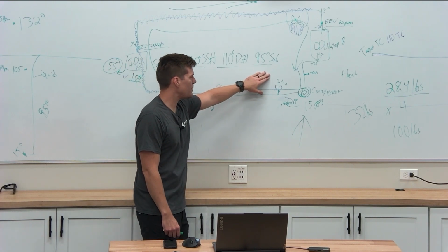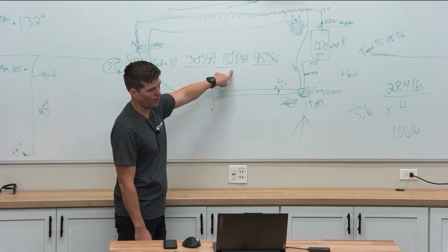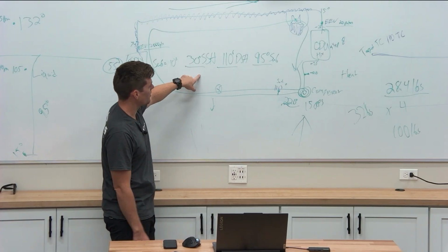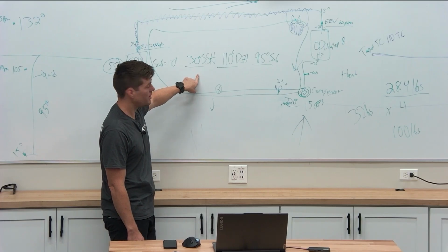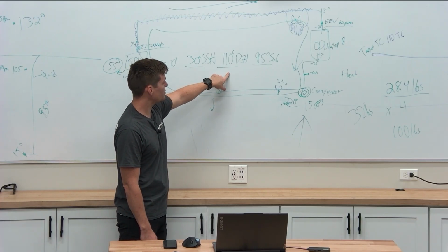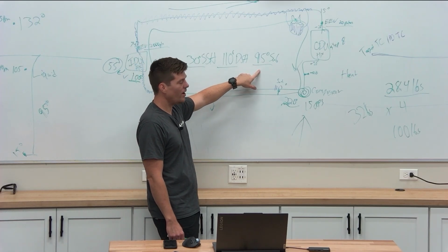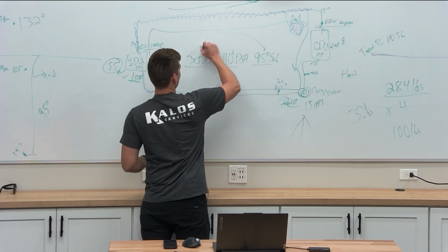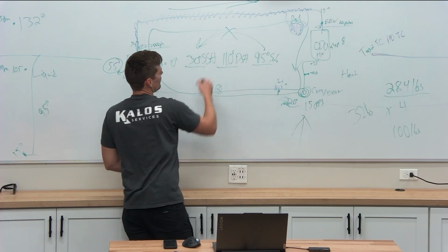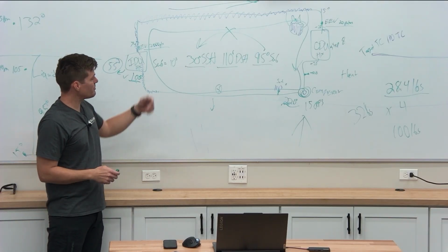All of these numbers paint a specific picture. This means not enough vapor, not enough oil. This means not enough vapor. Right? We know that. High superheat, not enough vapor. High discharge superheat, not enough vapor, not enough oil. High subcooling, wait a minute. This is not making it back to here. Or restriction. This would be restriction.